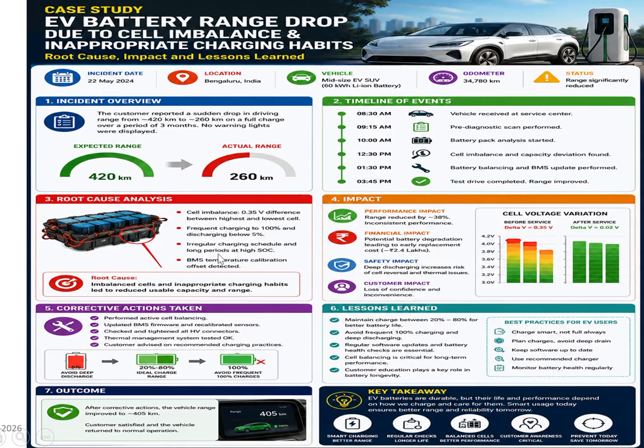Irregular charging schedules over long periods cause cell imbalance. BMS temperature calibration offset was also detected. These are some of the root causes identified during this case study.